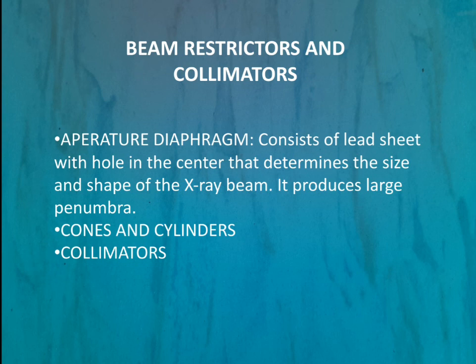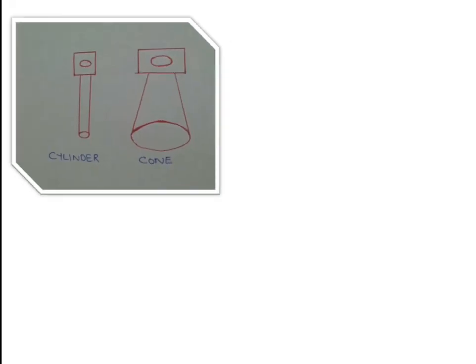Cones and cylinders are used for dental radiography and skull radiography. Collimators can be used for radiography of any part of the body. As seen in the image, cylinders and cones are attached to the window of the x-ray tube through which x-rays emerge. The cylinder or cone determines the area of exposure based on the area of the opening — only through this small opening will the x-ray come out.